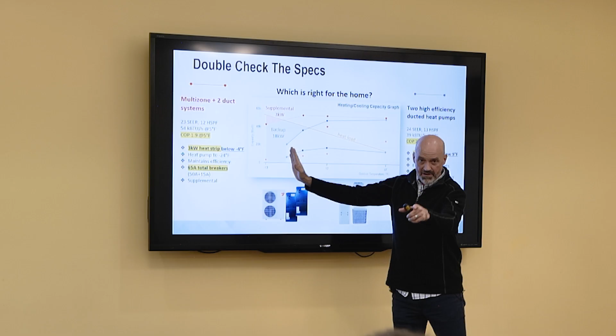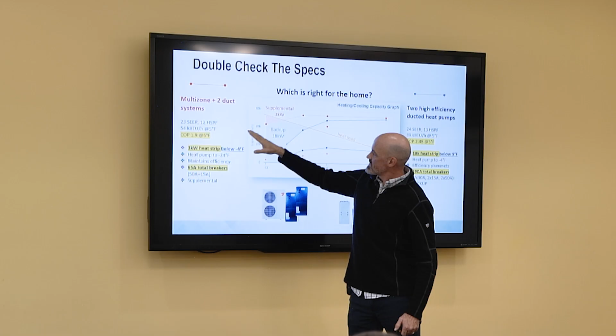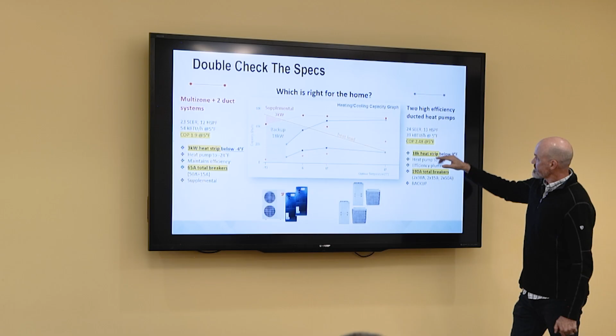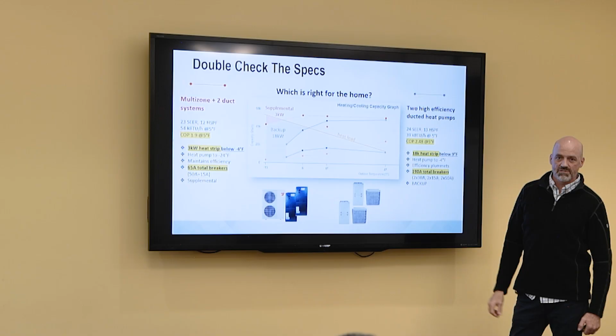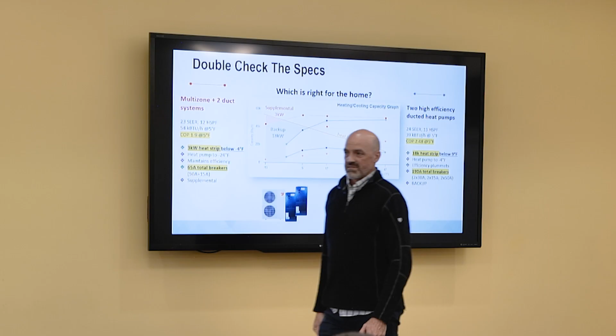Quick version: the red line is that capable system with a little bit of supplemental. The gray line is a competitive system, two of them, that stops operating, as Seth talked about. It turns off here, which means you need backup for everything else, an entire separate system to heat the house. This red line's supplemental system needs just a 3 kW heat strip, all in 65 amps of breakers on that outdoor panel. This doubled-up system with 18 kW backup needs 190 amps of breakers. This is where we start to get into 300 and 400 amp systems.